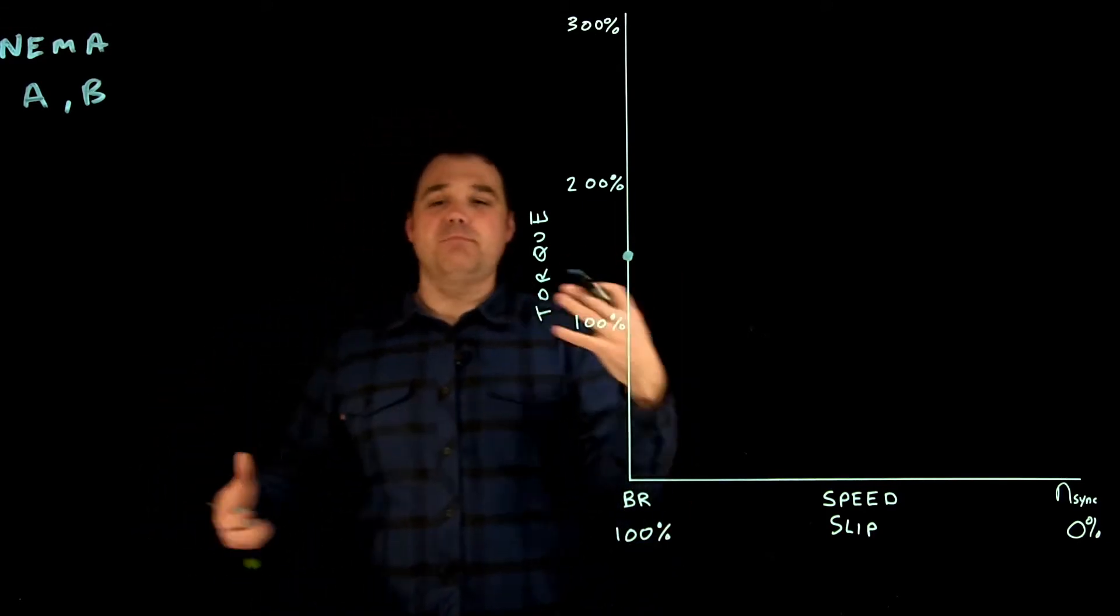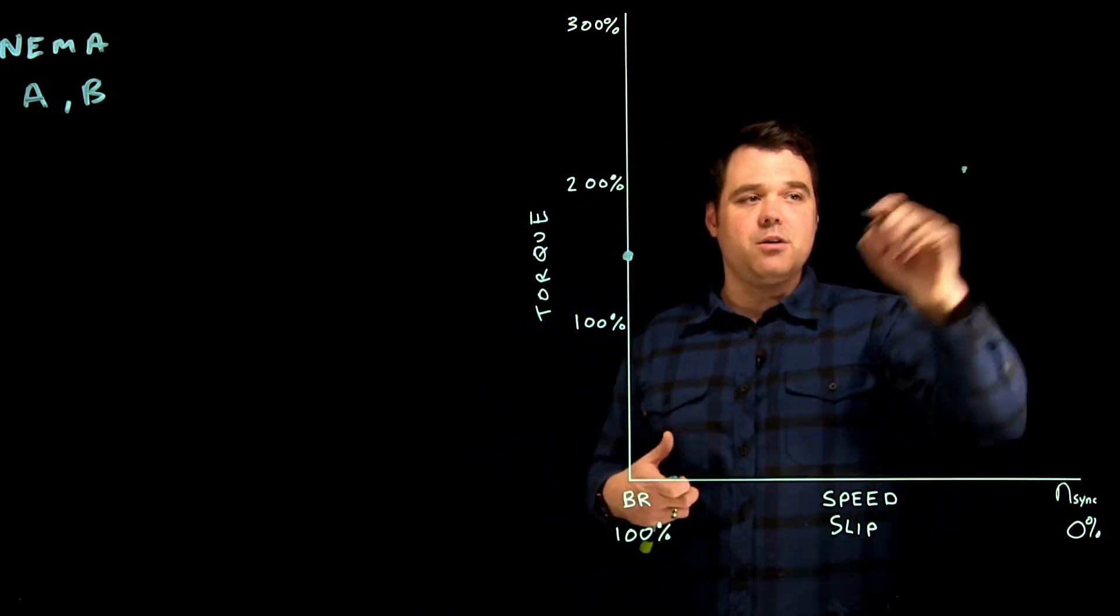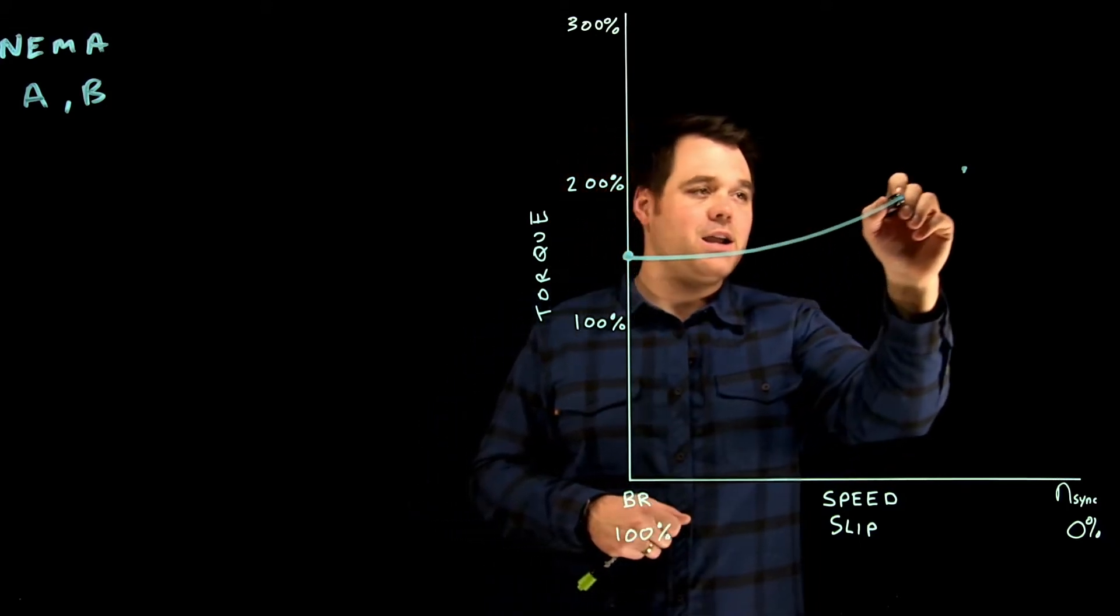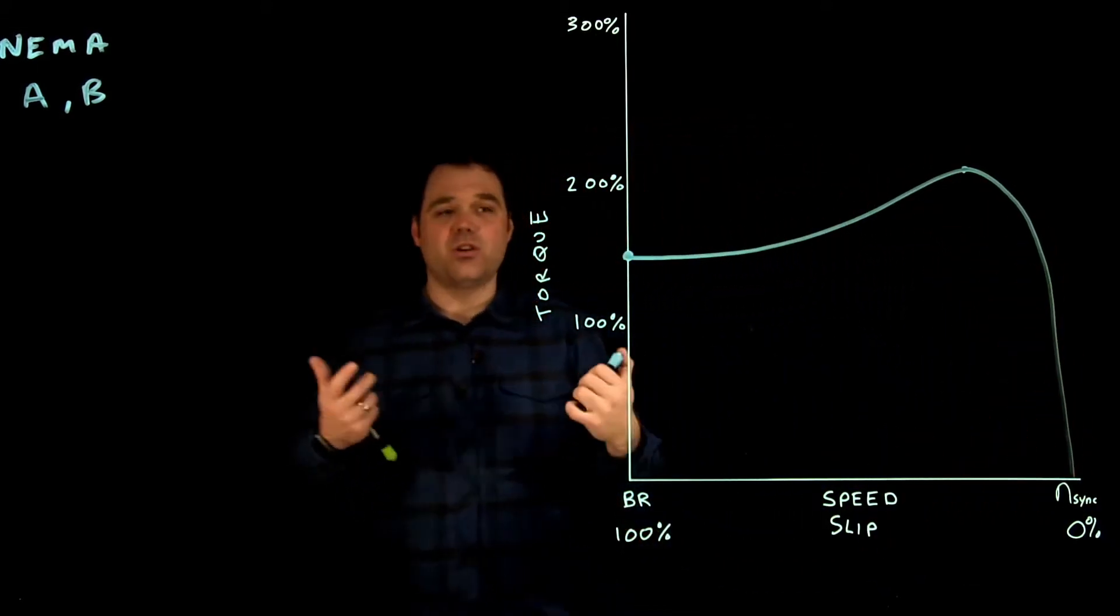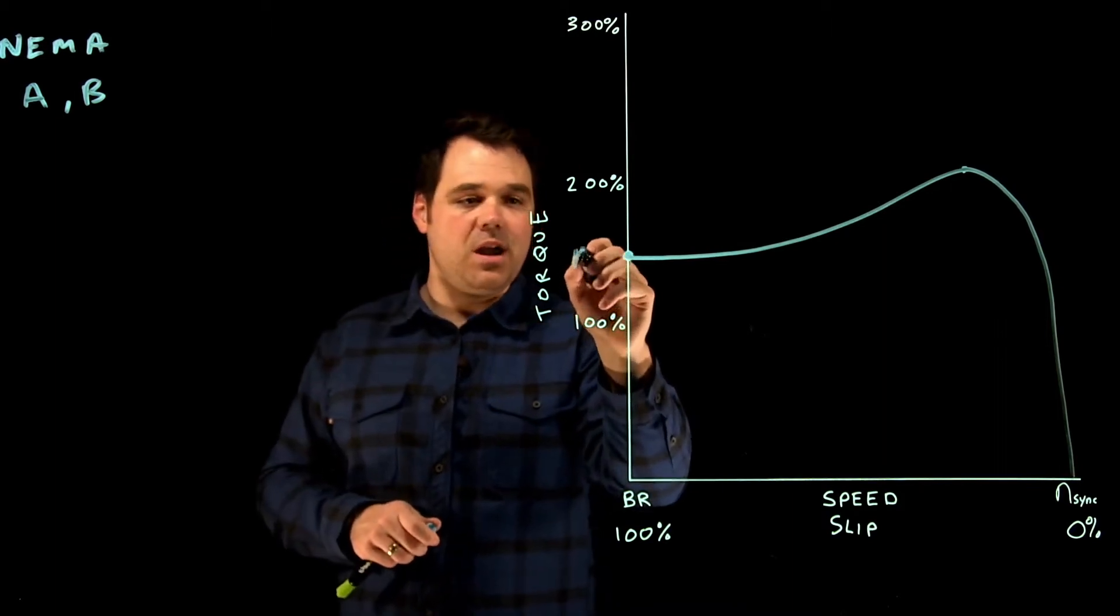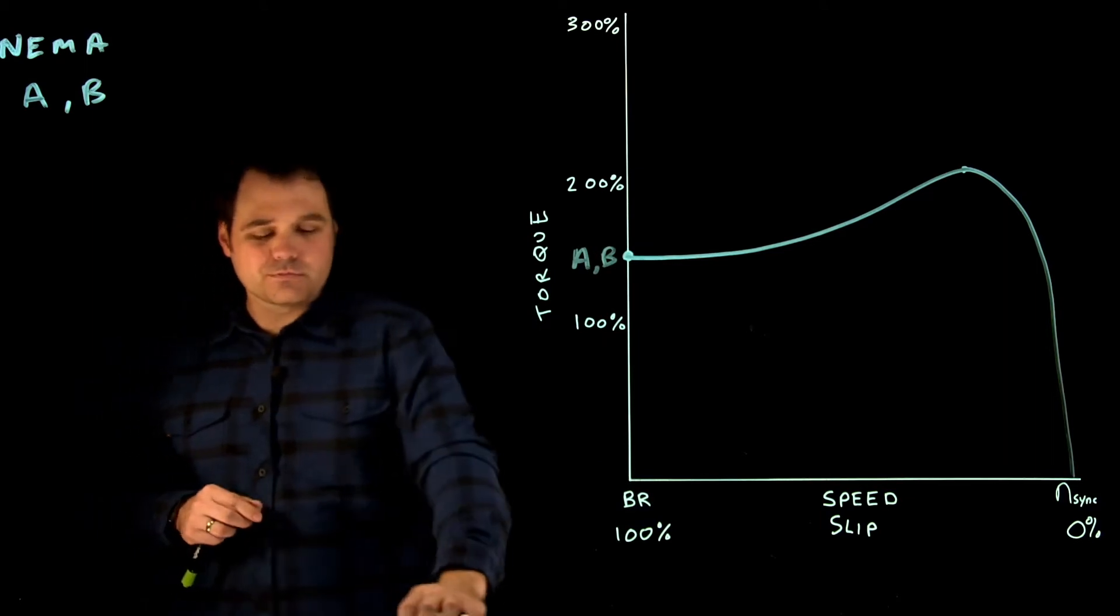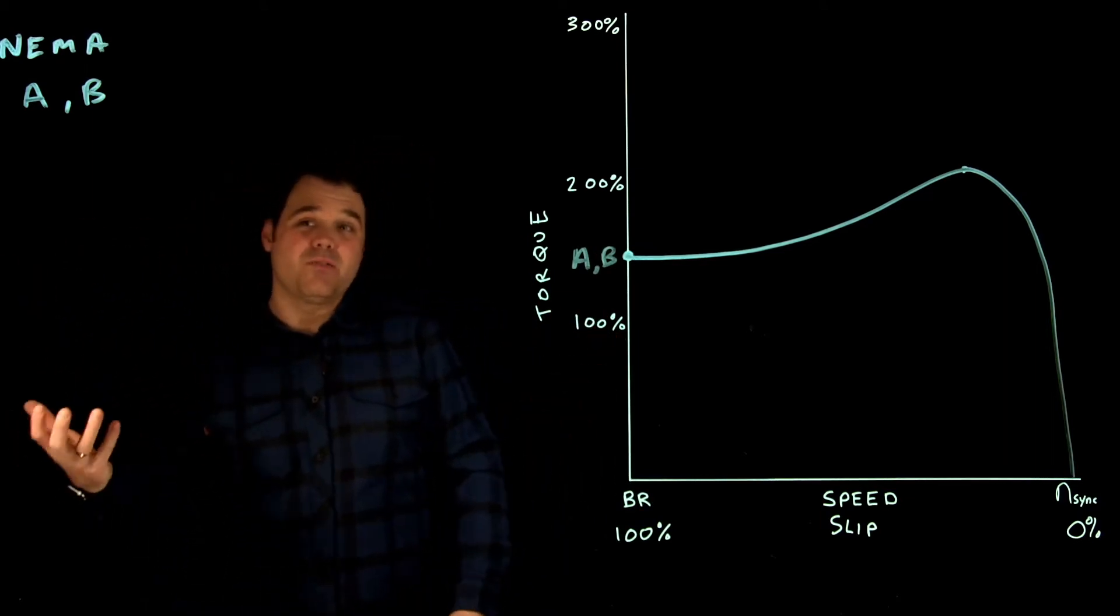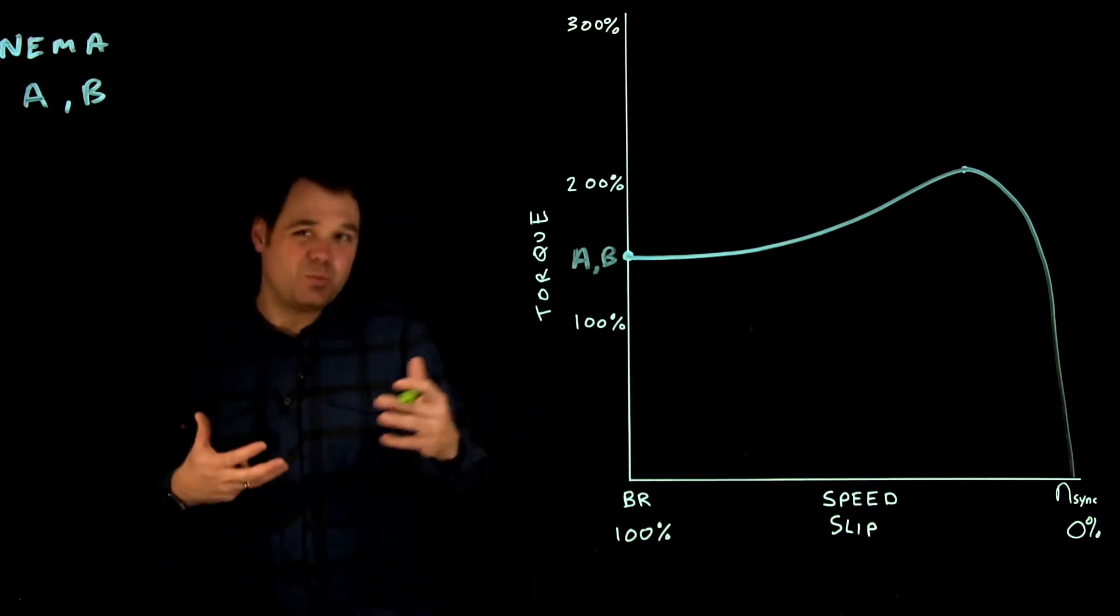And they both peak out around 25% slip at around 200% torque, and their torque curves look something like that. That would be a standard torque curve for a NEMA A and a NEMA B design rotor, of course slightly different. A being a little bit more efficient, B being a little bit lower inrush current and a little bit more common.